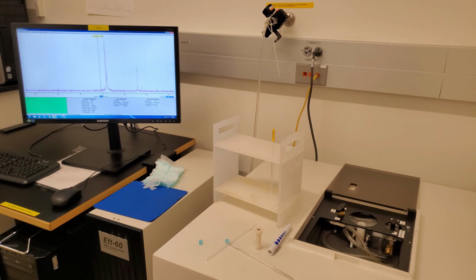The most frequent issue that you might run into is that a user reports that there is too much noise on the spectrum when running a sample. This could come from a number of issues, such as the spinner not spinning, the NMR tube is dirty or contaminated, or the magnet needs calibration. The best and fastest way to address this issue is by putting the water sample back into your probe yourself correctly, ensuring that the NMR tube is clean and correctly placed into the probe. Using a flashlight, ensure that the spinner is spinning. If it isn't, use the previous troubleshooting steps to fix it.